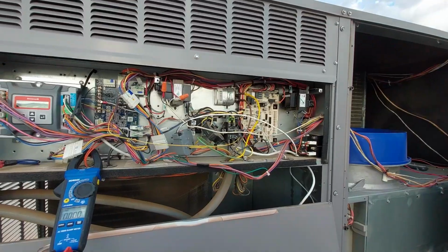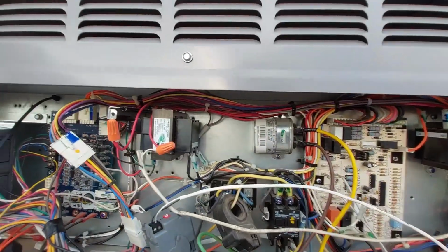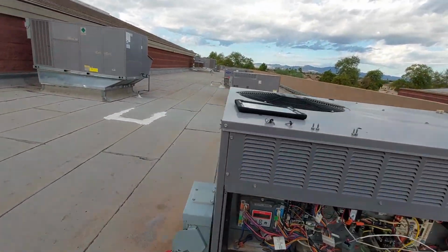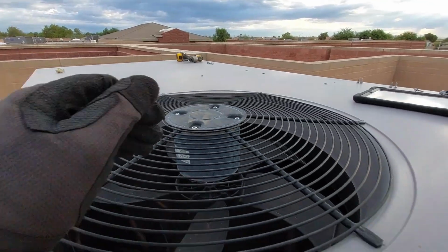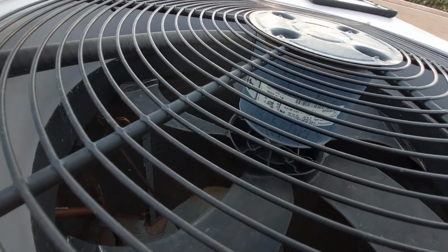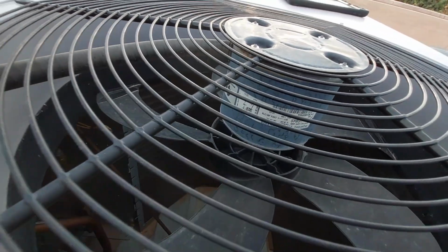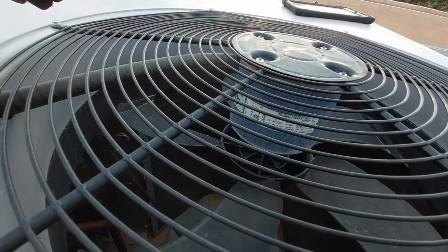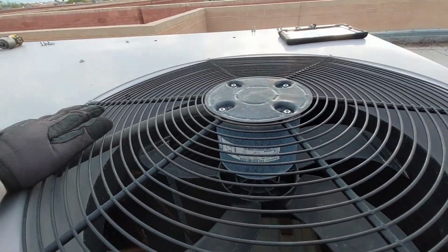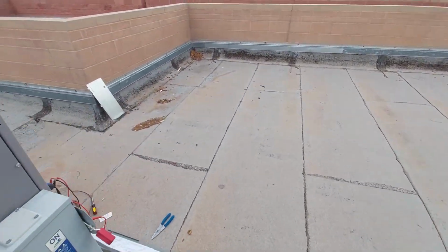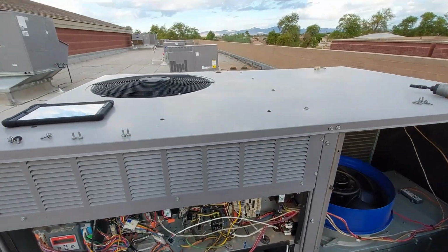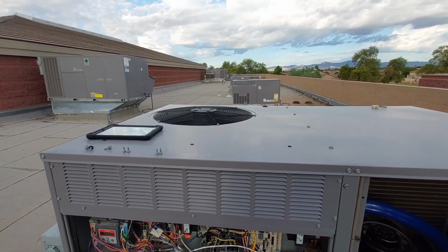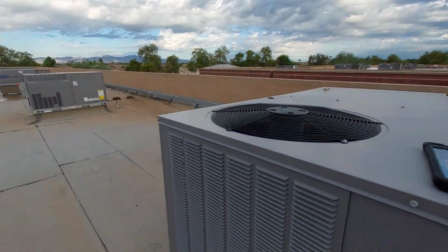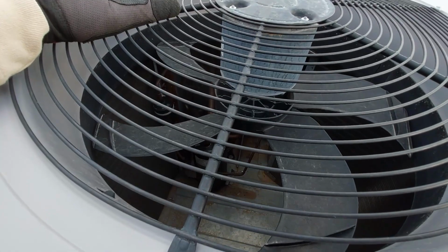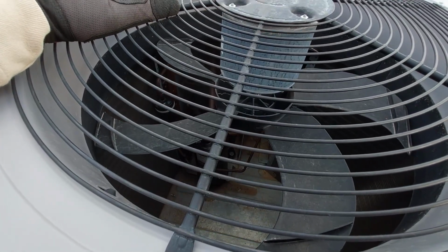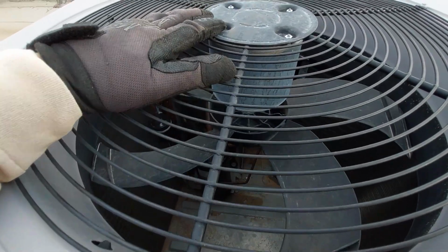So what that tells me is that the condenser fan motor is getting the proper amount of voltage, because I believe those are the only wires going to this motor here. Yeah, so right there on that sticker it shows black and yellow are the two line wires. So 280 on one wire, 280 on the black wire. Somehow that comes out to 460, which should have that condenser motor running. I'm wondering if maybe, let me open this up and let me check the condition of the shaft.